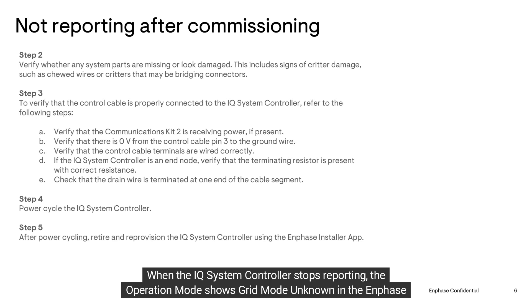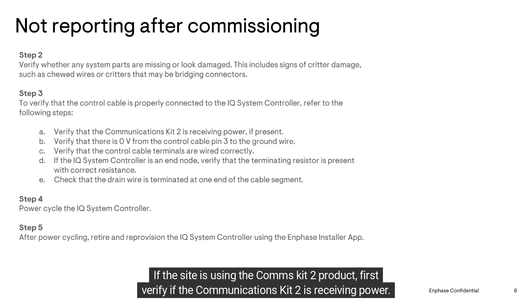When the IQ System Controller stops reporting, the operation mode shows 'Grid Mode Unknown' in the Enphase Installer App. If this warning shows, check to see if any system parts are missing or look damaged. Make sure that the control cable is properly connected to the IQ System Controller as well.